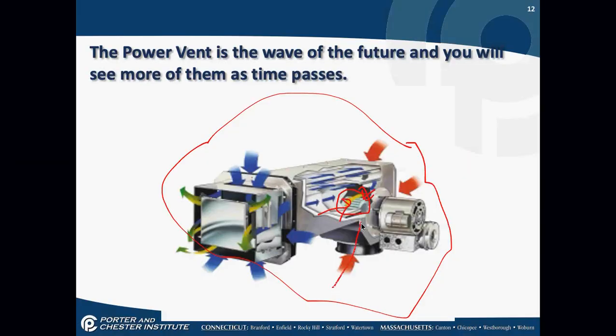Okay, so the exhaust comes in, gets picked up by this vent, okay, and blows out here. There's fresh air that's taken in from the outside to mix with that exhaust air to give us the volume to blow it away from the house. But this wheel that's in the center there corrodes. This motor shaft corrodes. Okay, there's a pressure sensor right on the outside of here. That is what senses whether or not we're moving air. That corrodes. So power venters are very subject to metal corrosion.